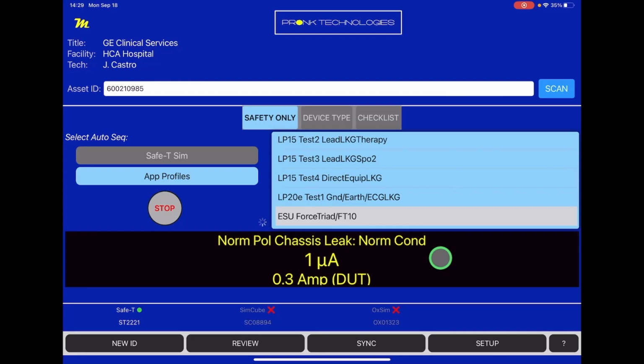And you can see on the app itself, it's going to be performing each test that's required per the manufacturer's procedure that we just created via the Mobilize app. So this first test here is a normal polarity chassis leakage test in normal conditions. And you can see here is the measured value it's getting.